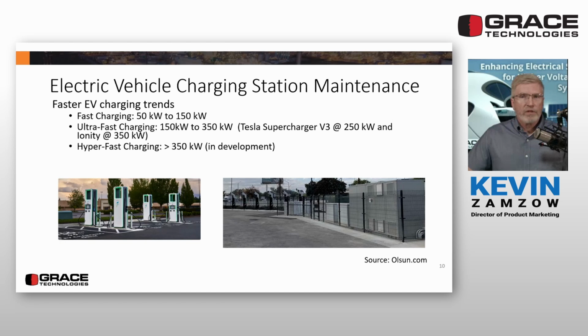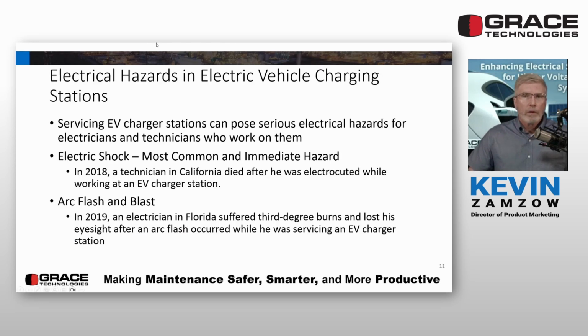Due to the large number of stations in a wide geographic area, maintenance of public EV charging systems is very likely to be outsourced. This slide is not meant to be sensational, but to drive the point that technicians servicing EV charging stations may be exposed to electrical hazards that can cause serious injury or death. In addition to EV charging safety components such as arc fault detection and interruption required by NEC 690.11, through panel testing for the absence of voltage helps reduce the risk of maintenance workers who may not be as experienced as qualified utility and industrial electricians.